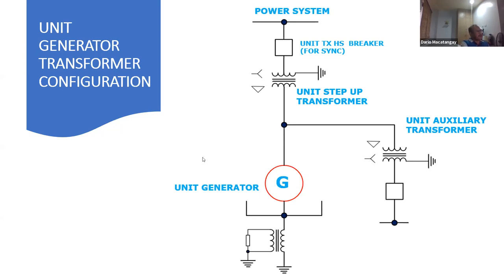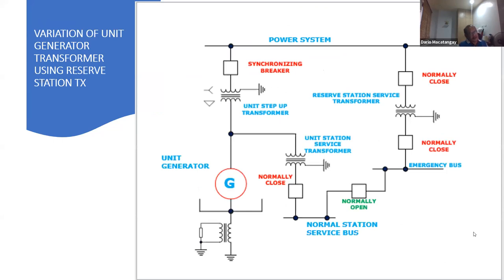Now the second type, which improves on this: in nuclear power plants, some of them have introduced this reserve station service transformer, okay? So although you can see that the breaker here on the generator is on the step-up transformer, you can still maintain this, and you can still maintain service to the plant during shutdown, because you're actually powering it from this reserve station service here, right?